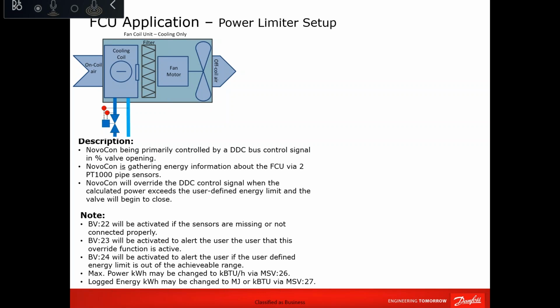So Novocon is gathering energy information about the FCU via the temperature sensor. Then Novocon will override the control signal when the calculated power exceeds the user-defined energy limit, which means you can use the Novocon as a normal valve to control based on the room temperature and so on, until the moment the power exceeds the limit that you have set from the BMS in the Novocon. So doing so, it will limit and save a lot of energy. If you do this for every unit, 5% or 10% of the cooling power directly affects the cooling energy. It's not like pumping savings or delta T savings, which need to be calculated to take effect, but this directly affects the power itself.